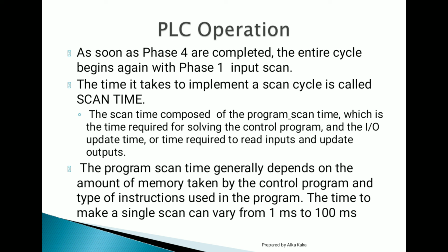The time it takes to implement a scan is called scan time. So what is scan time? It is the time required for solving the control program that the user has written, plus the input and output update time, that is, the time required to read the inputs and update the outputs. All this time combined, reading the input, program scan time, and sending the output update, becomes the scan time.